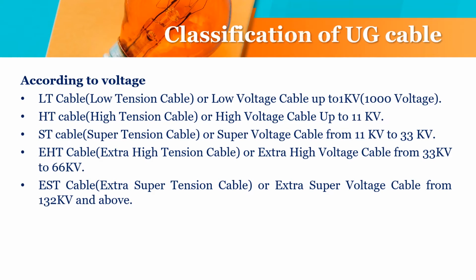According to voltage: LT cable, low tension cable or low voltage cable, up to 1 kV, that is 1000 volts. High tension cable or high voltage cable, up to 11 kV. ST cable, super tension cable or super voltage cable, from 11 kV to 33 kV. EHT cable, extra high tension cable or extra high voltage cable, from 33 kV to 66 kV. EST, extra super tension cable or extra super voltage cable, from 132 kV and above.